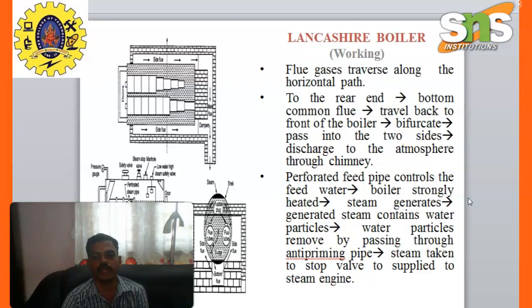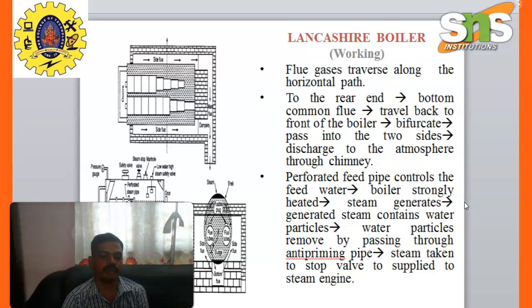A perforated feed pipe controls the feed water. The boiler shell is strongly heated and steam is generated. The steam contains water particles, which are removed by passing through an anti-priming device. The dry steam is then taken to the stop valve and supplied to the engines.